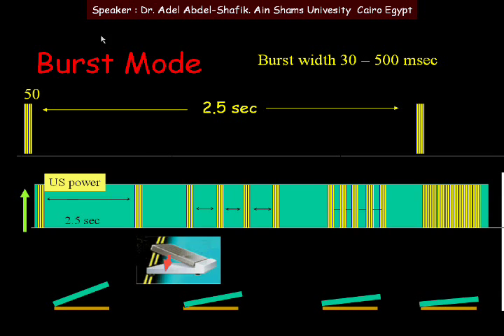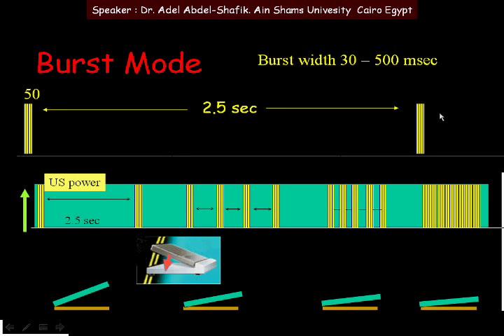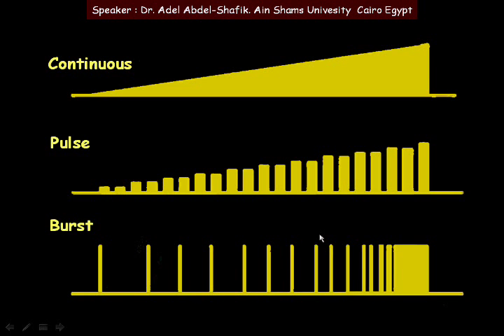In burst mode, at the early stage of pedal position three, the off period is 2.5 seconds. As you depress the pedal gradually, the off period becomes shorter and shorter. At maximum depression, the off period disappears entirely and it becomes a continuous phaco mode.